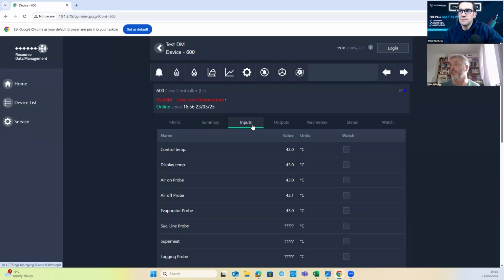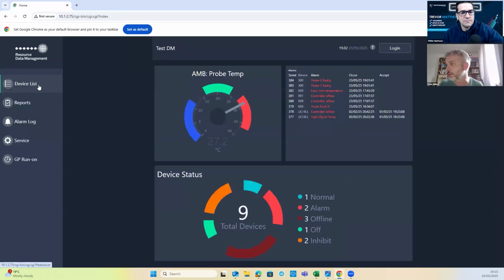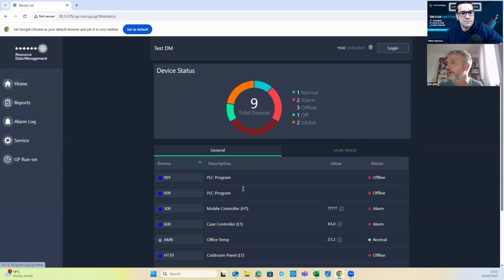So you're going to go into the unit menu and you're going to compare the number that's set in there to what type of probes you've got fitted. So for me, I'm going to do it right now as we're speaking. I know that I've got PT1000 fitted, and I know that they're type 0 on an RDM controller. So I'm going to set that. And when that refreshes itself in a minute, we'll see how our other controller's doing as well while we're waiting for that. Oh, look at that. It's actually logged itself on. There we go. So number 300 there is the controller that I just connected.